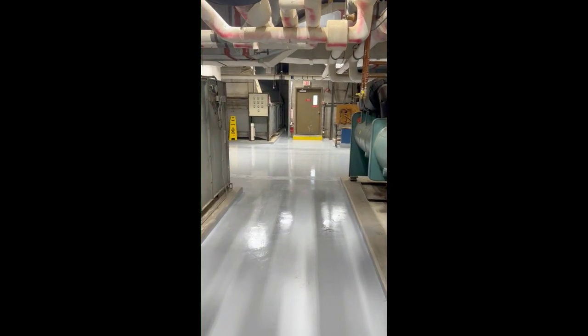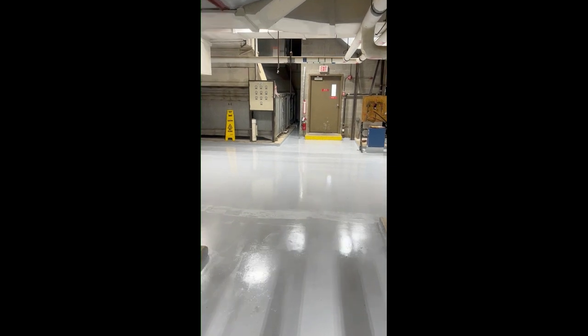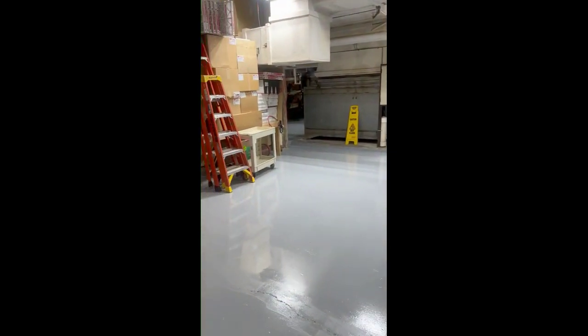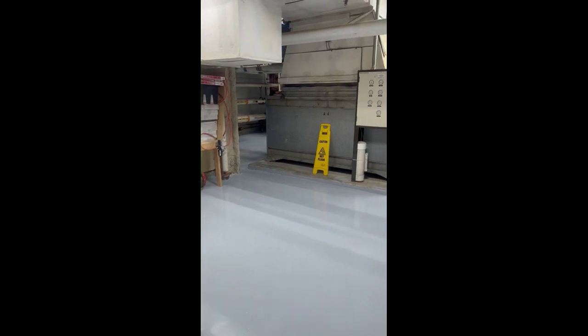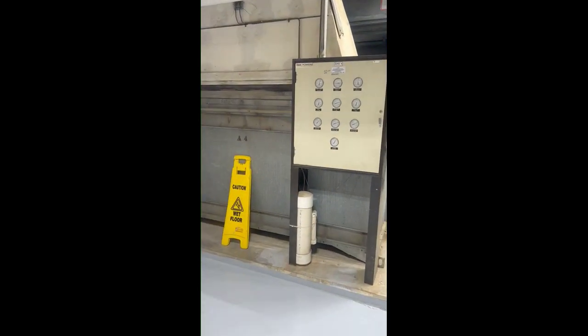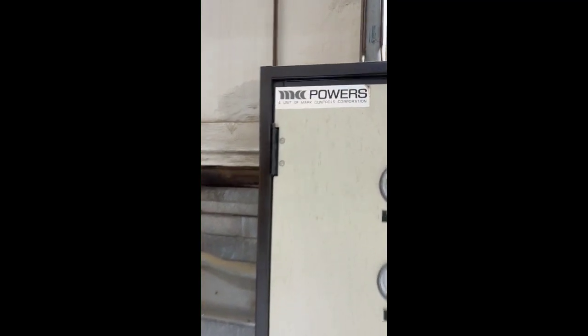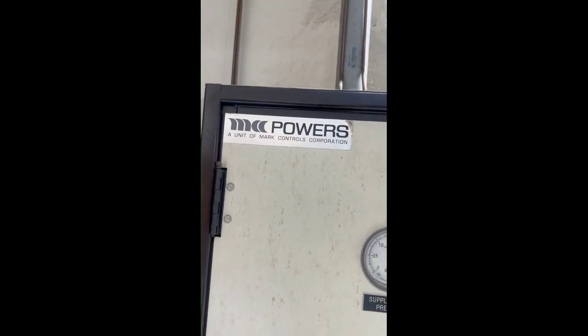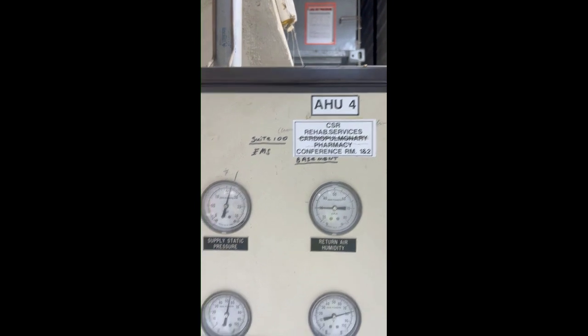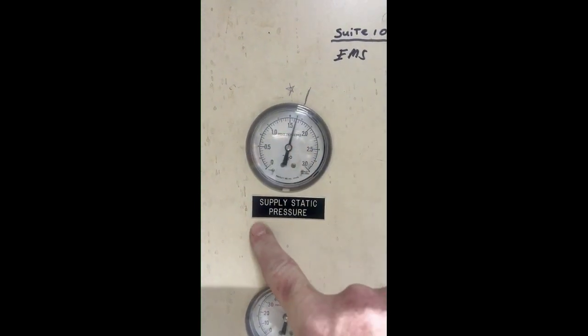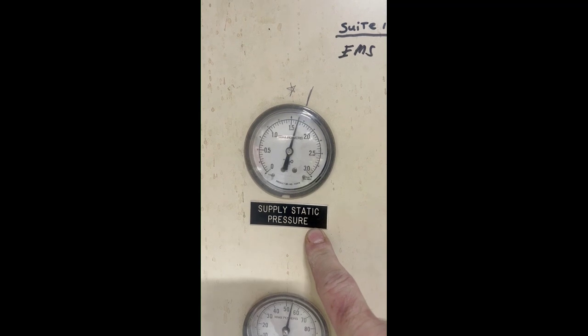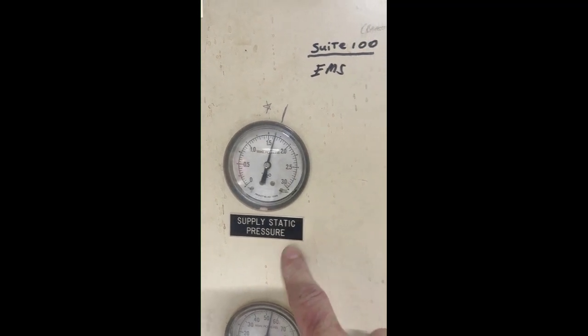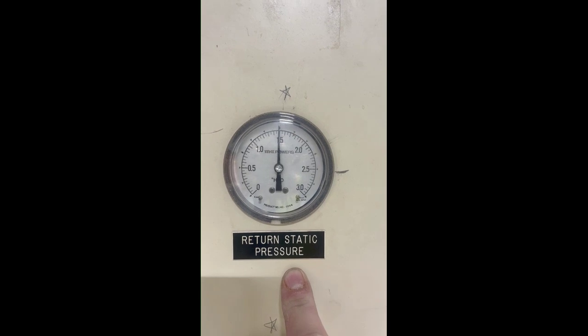Continuing around the penthouse mechanical room, a lot of the assets that are up here, those of you who have a handle on the old equipment, it's a pneumatic transduction system, and the pneumatics in this case are Powers. Powers is a manufacturer of different air controls and electric transduction controls. This is my air handler. One of the things that I'm looking for is, do I have supply static pressure, meaning I have air pressure going to the building, and do I have return pressure coming back that completes the circle. Those are some things that I look at, and the unit is running.